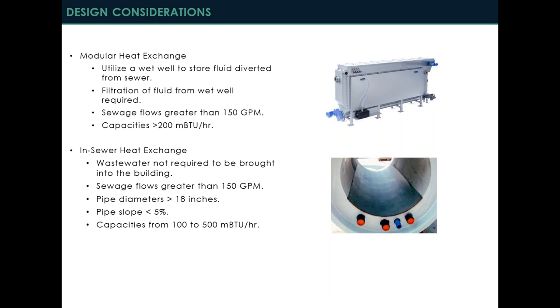So the focus for single-building applications is going to be on modular heat exchange options. Some significant space is required — while you may take a cooling tower off the roof and open up that space, there's a trade-off: you need more mechanical room space in the basement or garage level. You also need to think about what type of screening you need, since any number of things could be flowing through a sewer system. A lot of time needs to be spent figuring out the best screening system to apply, and then determining what type of heat exchanger makes sense — whether shell and tube or plate and frame — as these things will be different from one project to the next.